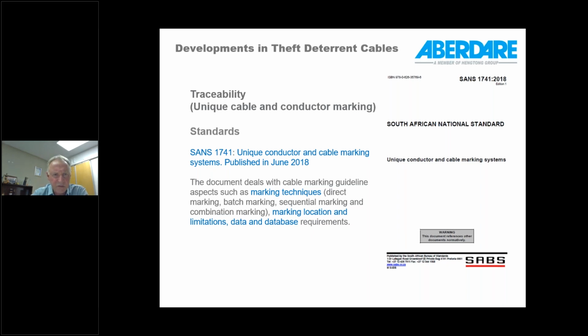So there is a SANS standard that was developed and published in 2018, which deals with unique conductor and cable marking systems. This document deals with cable marking guideline aspects, such as the marking technique, marking location, the limitations, the data, and the database requirements. This is quite a generic document, so it doesn't go into the absolute detail of, for instance, the tape marking system. But at this particular point, the only solution that is in the market from local cable manufacturers is this tape marking method. So the South African Cable Association has a document which describes the particular details of this tape marking system in more detail.